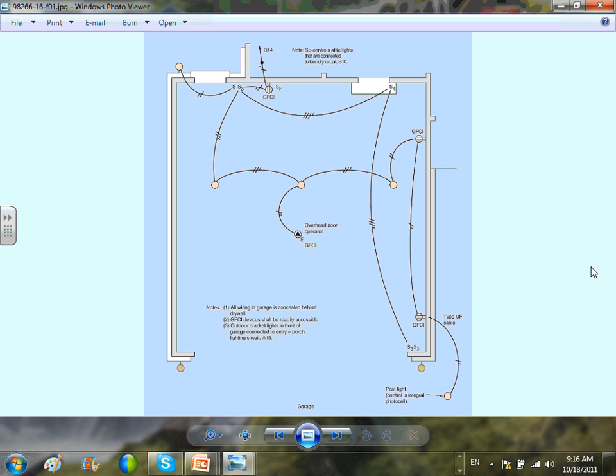Okay, this is just the same circuit, guys, that we did. Any comments? Any question about this circuit? Now, next, my friend, you're going to take this circuit and do a point-to-point wiring for it. Just to remind you, when we do a point-to-point wiring, every outlet or every light needs at least two conductors, a hot and a neutral, right? A switched hot and a neutral if it's a light, a hot and a neutral if it's an outlet.